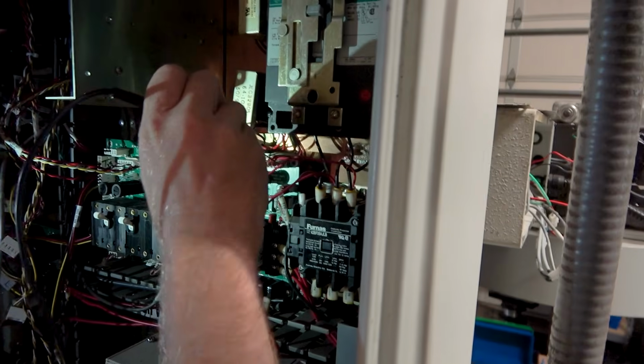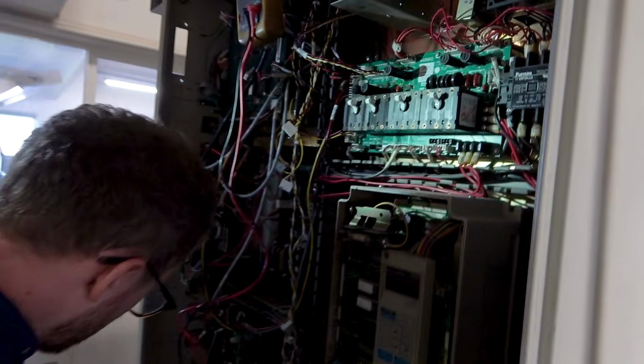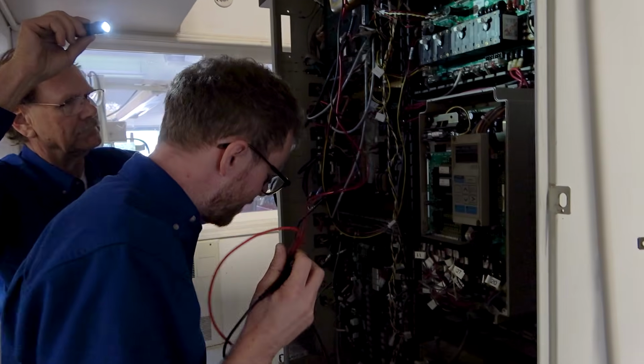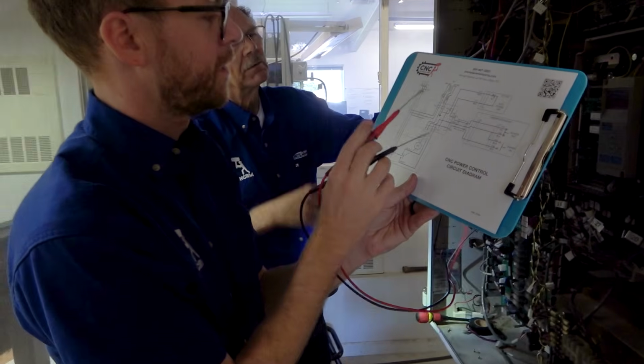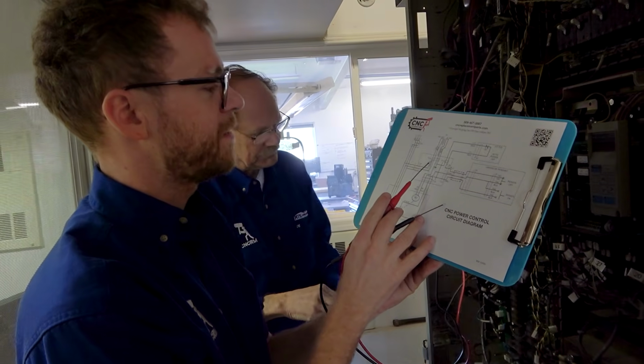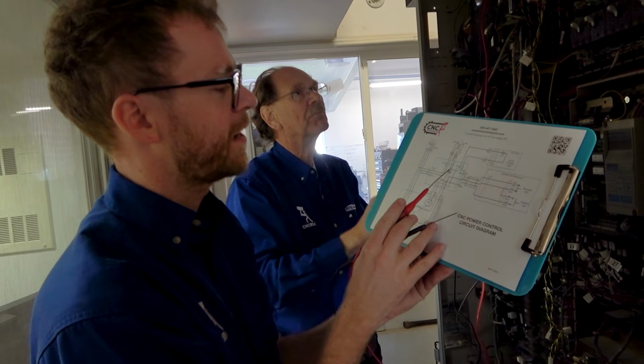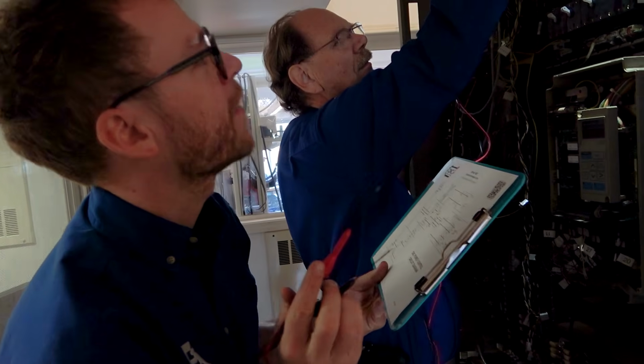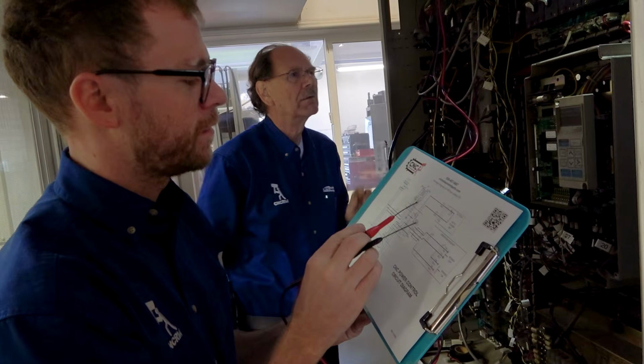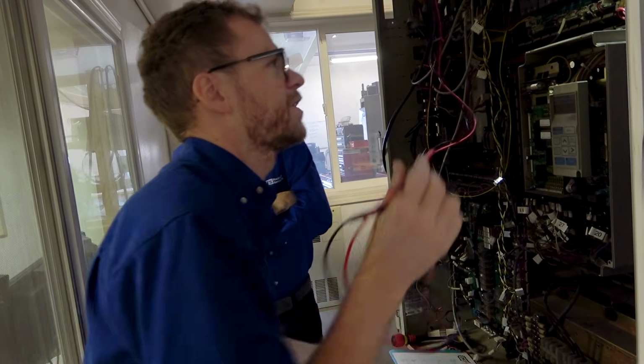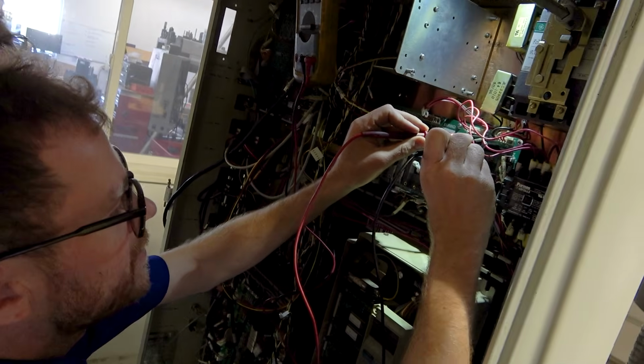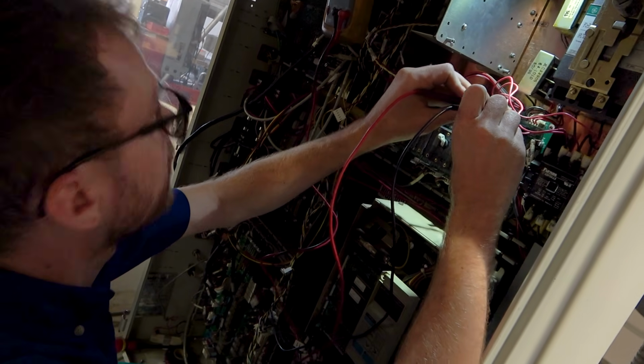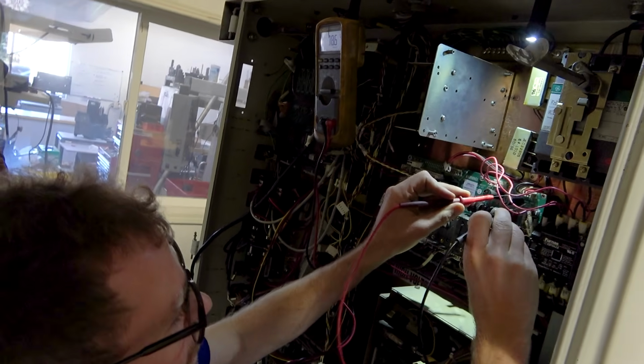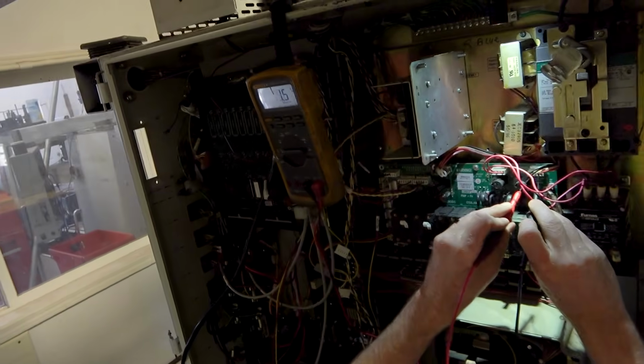So we've got 5 plugs here, and if this is labeled correctly, the 2 on this side should be the incoming power, and the 2 on that side should be the local. So let's check and see. I've got my voltmeter. I love these stab-in leads. If you're doing CNC machine troubleshooting, the stab-in leads are great. 250. Okay. Now let's check these two.